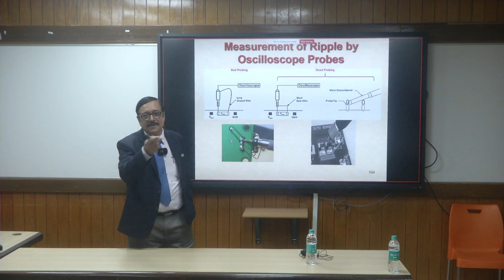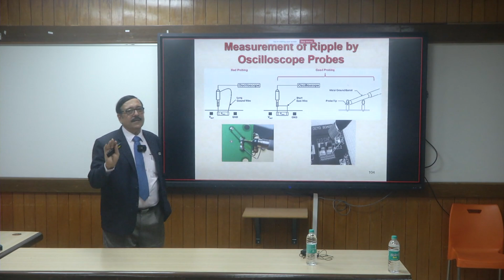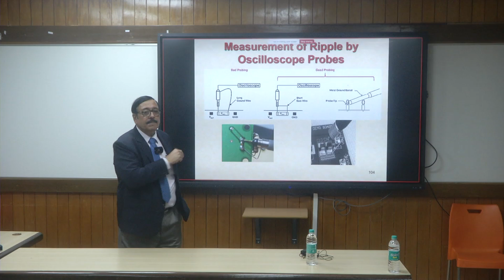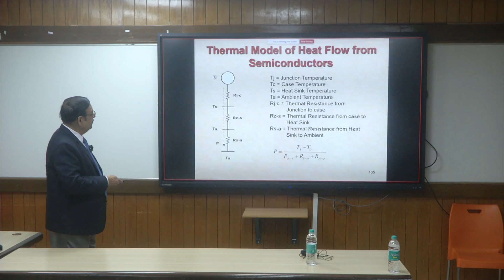It defies the laws of inductive circuits. You can't have a rapid change of current spike. It is most probably a pickup that you are seeing. If you observe it carefully, you will see that it is not there. If you have a Hall effect sensor based probe, most of the time it senses the external flux and picks up. So one way to check is to install a very low resistance somewhere, put your oscilloscope probe across it, measure the voltage, convert it into current. You will see the spikes are not there. Okay, I think I have come to the end.